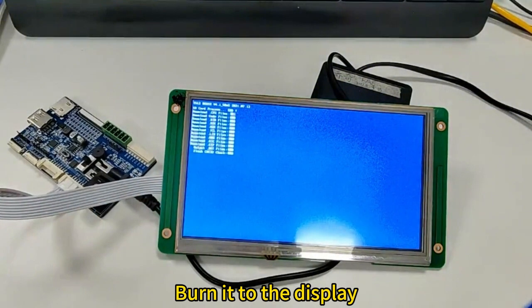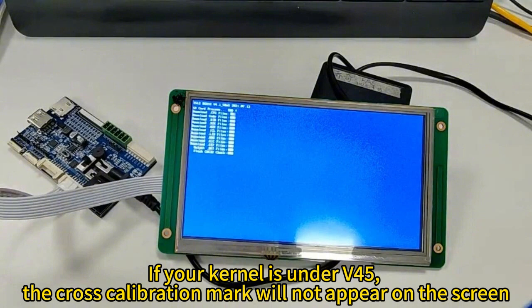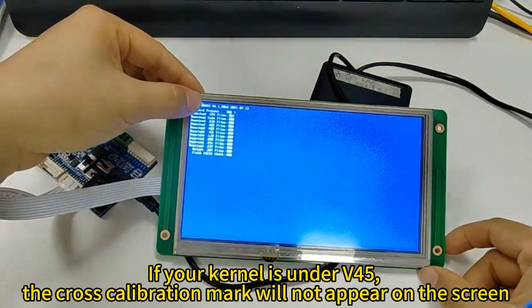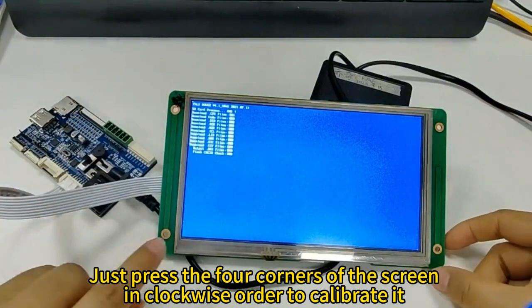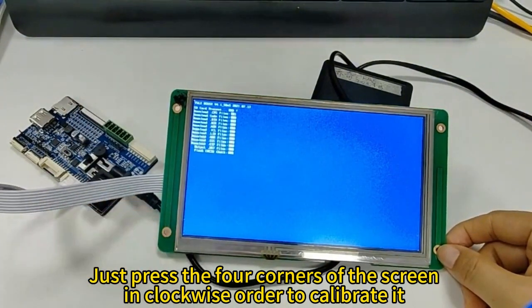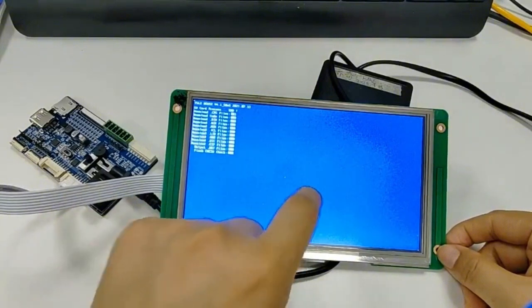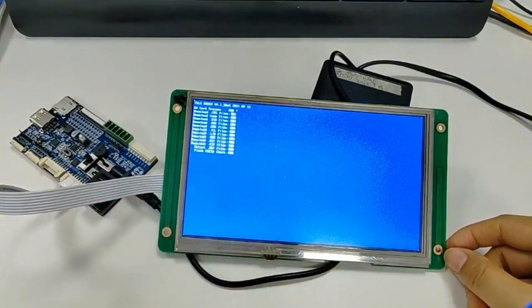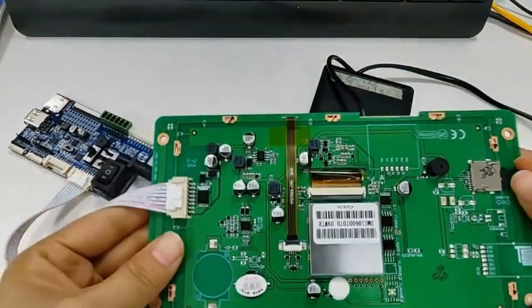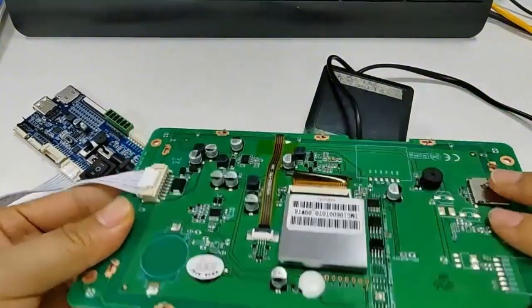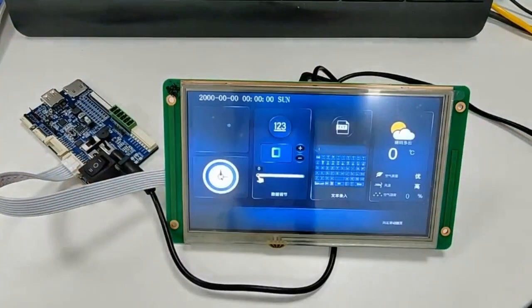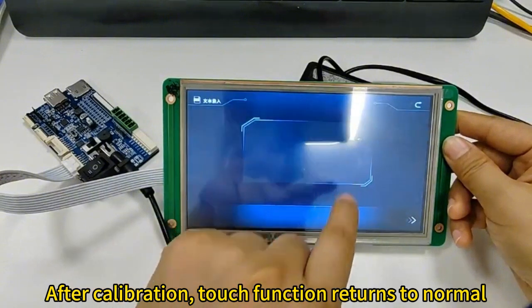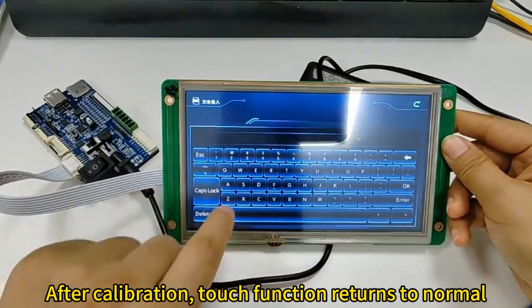Burn the CFG to the display. If your kernel version is below V45, the cross calibration mark will not appear on screen. In that case, press the four corners of the screen in clockwise order to calibrate. After calibration, the touch function returns to normal.